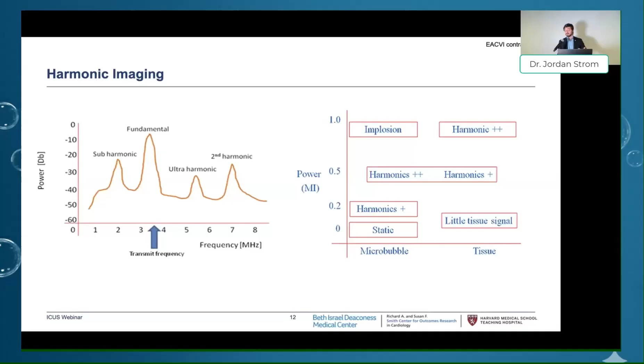And at very low MI settings, where the ultrasound power is very low, particularly below 0.2, but even less than that, we have very little activity from the tissue itself, and we get very little signal from the tissue, but we get a nice harmonic signal from the bubbles themselves, and that allows us to create this effective tissue contrast. In particular, we're able to really focus on the activity and the motion and the appearance of these bubbles. It also allows us to keep the bubbles in circulation for a longer period of time. Now, why might you want a little bit of a higher MI?